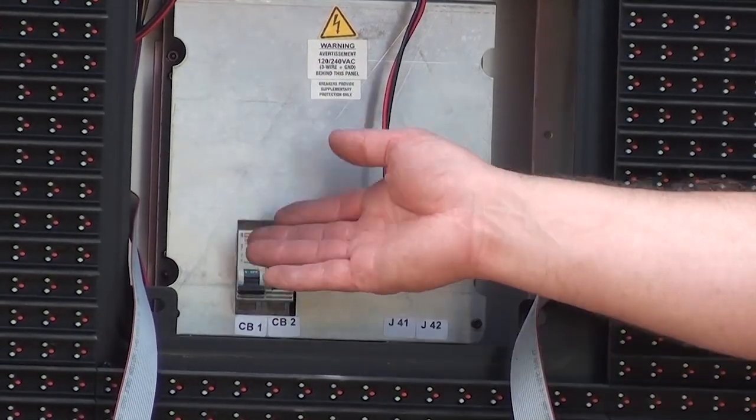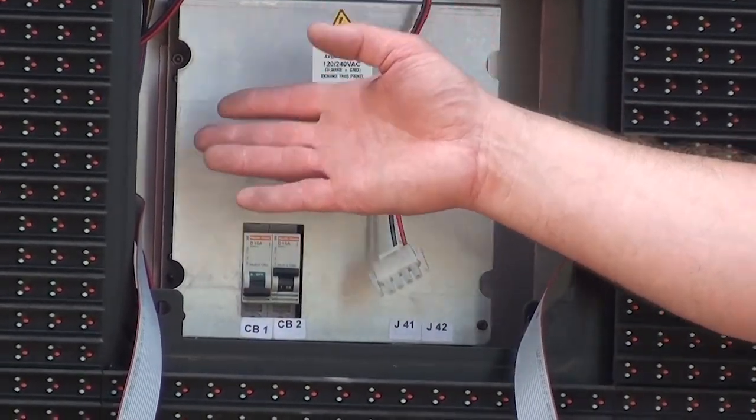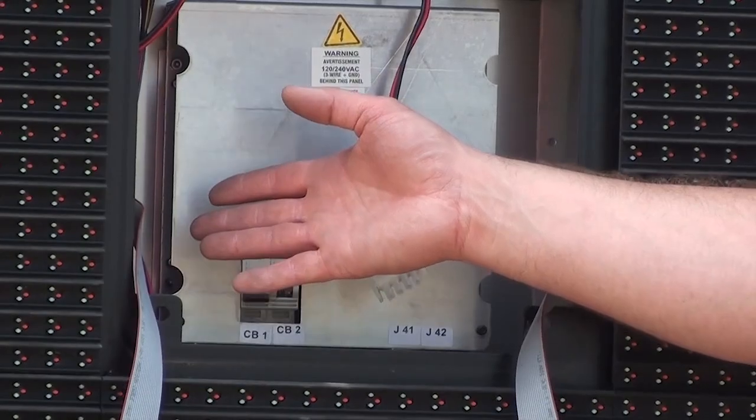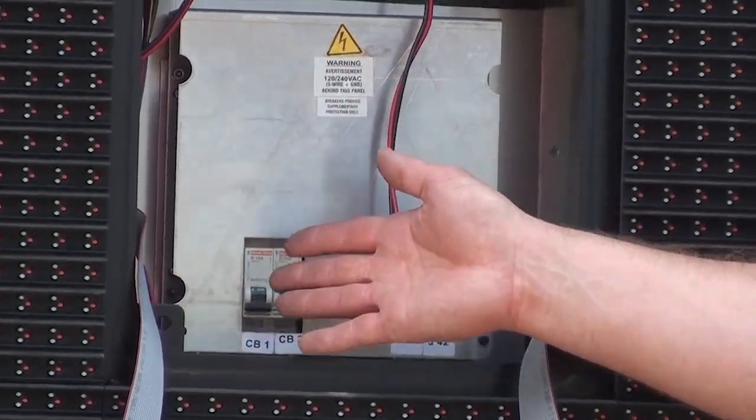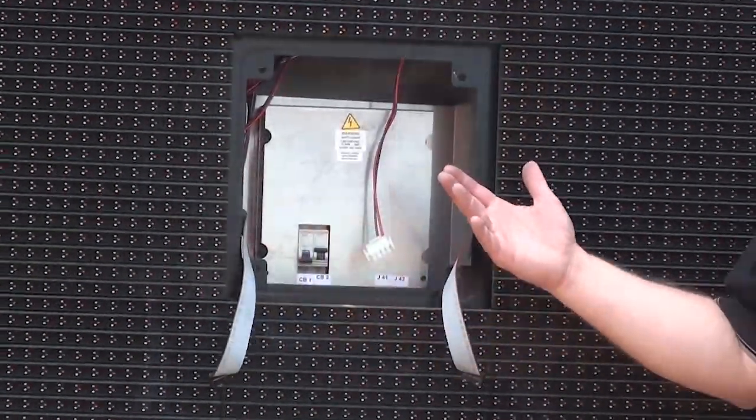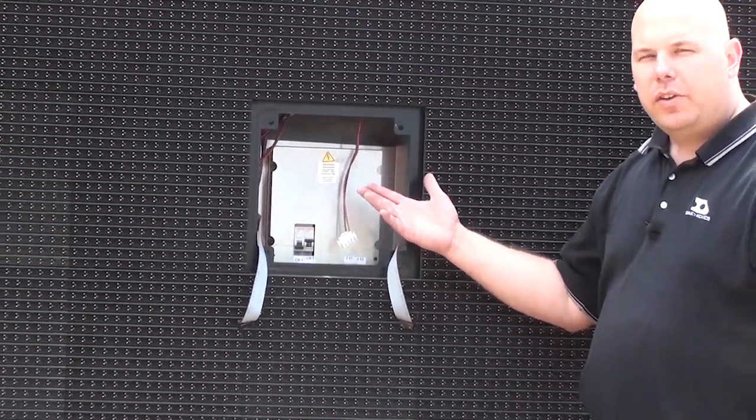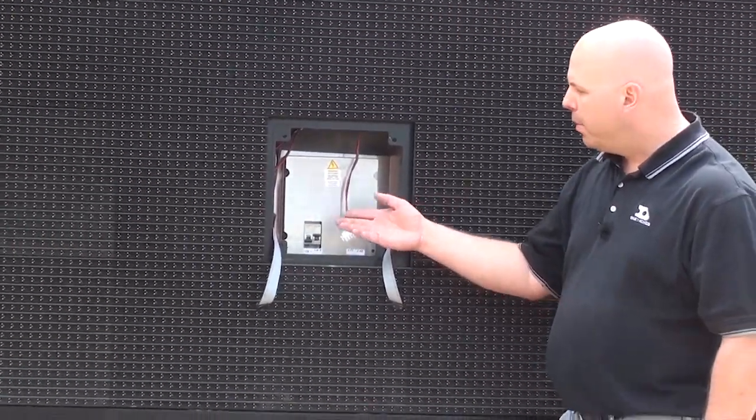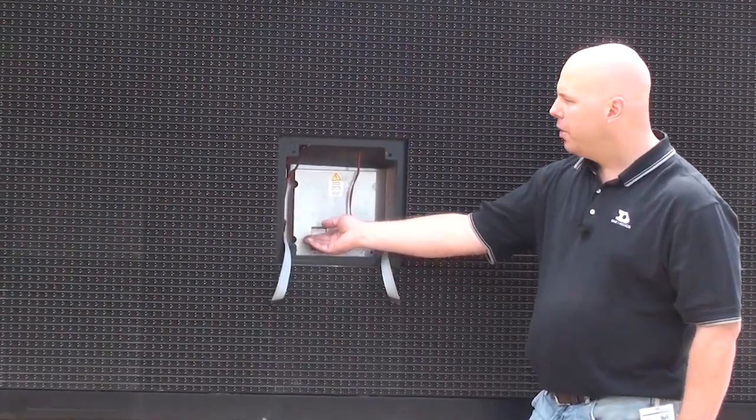Now I'd want to do some additional troubleshooting to see if any of the wires were cut or nicked. That may have caused that. Now that I've checked out the cables, I don't see any other problems. I'm going to go ahead and reset that breaker.